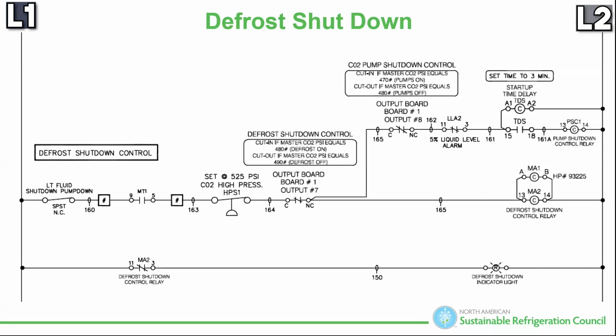If I take my meter and put my red lead and black lead on L1, on one wire, or across a fuse that's good, how many volts will I read? Zero. There's no difference of potential there, no energy. But if I move that black lead over to L2, now I read 208 volts because there's a difference of potential through there.